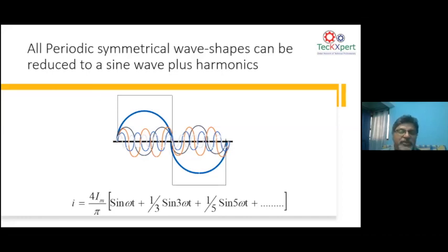When I say quantity, I mean magnitude. The sine wave will have, let's say, a fixed magnitude of I max. But the third harmonic will have a magnitude of I max divided by 3. Similarly, the fifth harmonic will be I max divided by 5. So when you split any distorted waveform by Fourier transformation, it will be the fundamental wave plus the odd harmonics: the third harmonic, the fifth harmonic. Third harmonic means 150 cycles, and fifth harmonic means 250 cycles.